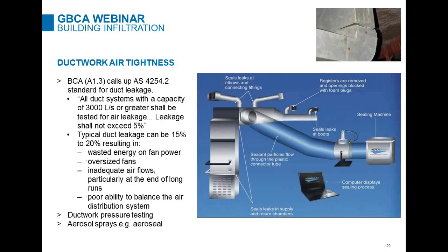The building code actually does now call up the Australian standard for duct leakage. For those ducts over 3,000 litres a second, they should be tested, and the leakage should not exceed 5%. Well, actually, typically, ducts can be leaking 20% of the air that's put through them, and you can imagine how much energy is being wasted, both in terms of the direct fan power, pushing the air through those leaks, rather than to the space where it was intended to be delivered, and also by the chillers in cooling that air down that gets wasted by being vented in the plant room or some other duct run in a non-conditioned space.